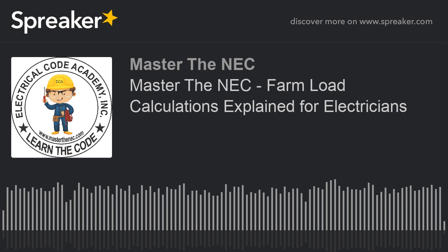All right, so in that scenario right there, this has to do with a common service. So a service that would be, let's say, going from a transformer, a service drop coming down. That's a common service, and that's going to be supplying both the dwelling and the other than dwelling loads. If that's the case, and I have electric heat in the dwelling and electric grain drying system somewhere on the property, on the farm, and it all being supplied by that common service, then just remember that when I'm doing that dwelling calc, I cannot use an optional method. It has to be the standard.